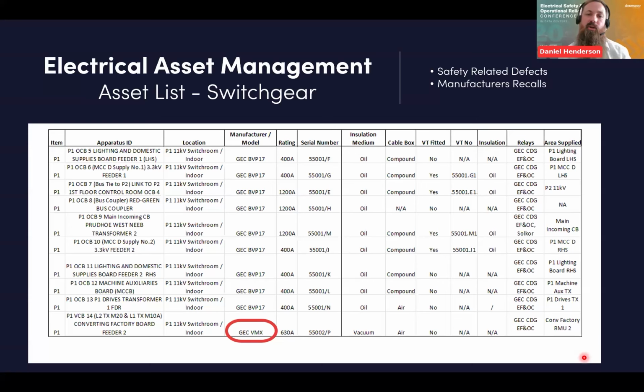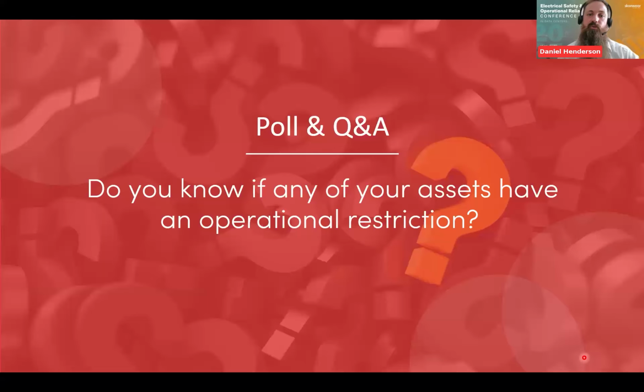As I'm looking now, I know my equipment's not supported, so I can't go to the manufacturer in my example. So I've looked in NEDeRS for any operational restrictions, and I've identified that this one particular bit of switchgear is subject to a suspension of operation practice, linked to partial discharge. So I'm starting to think about, firstly, how does this impact the people that work on and near that equipment? And then secondly, how does this impact business continuity, which we'll look at.